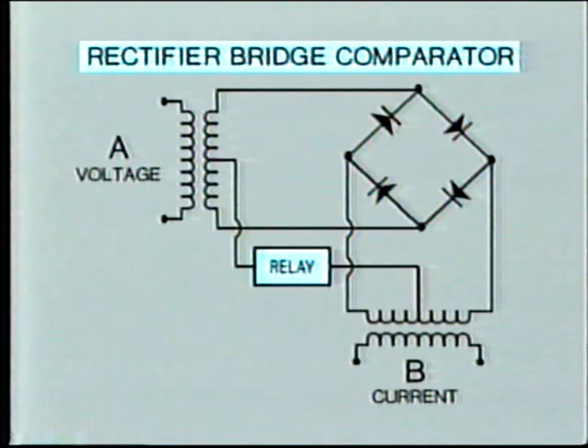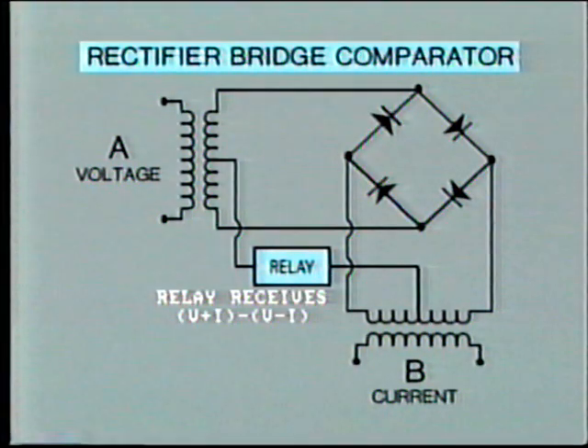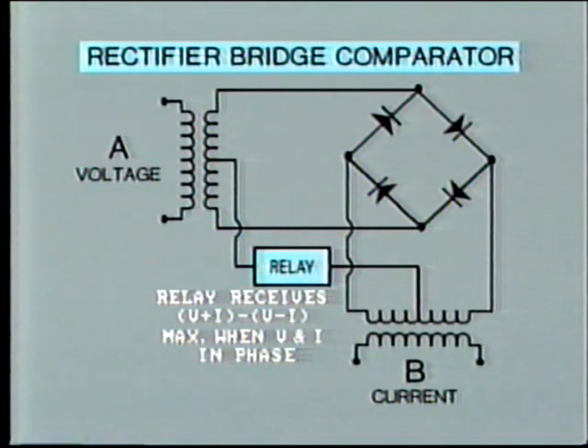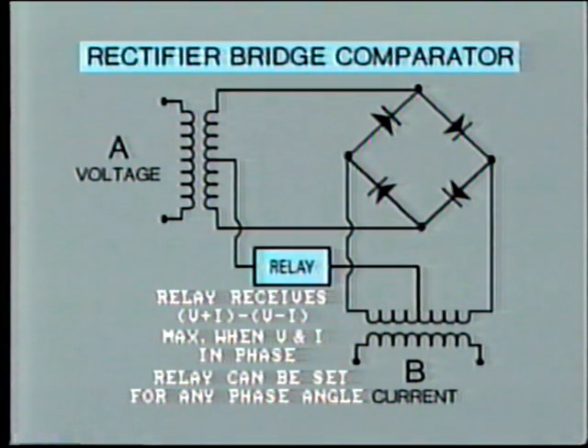Directional relays also use the rectifier bridge comparator. This compares the amplitude of the two inputs, say voltage and current. The relay receives the signals V plus I minus V minus I. The maximum value is obtained when V and I are exactly in phase. The specific value can be determined for different phase angles, thereby allowing the relay to be set for any desired phase angle.